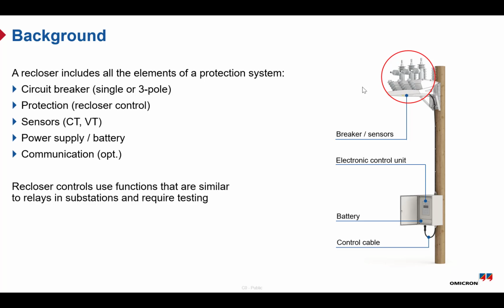In many cases, communication is also included, allowing the recloser to be connected to SCADA systems for monitoring, control, and data collection. All these components are connected through control cables that carry measurement, status signals, and control commands. So even if the recloser is installed out in the field, it performs the same role as a fault protection system, and that's exactly why proper and complete testing is essential.